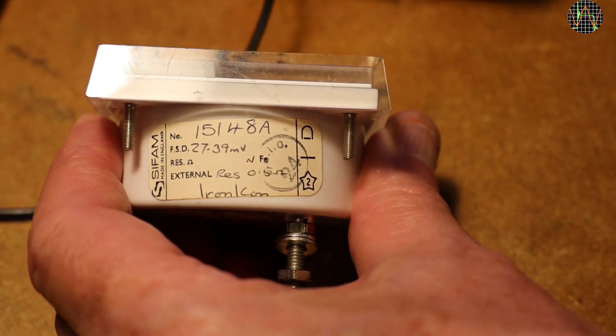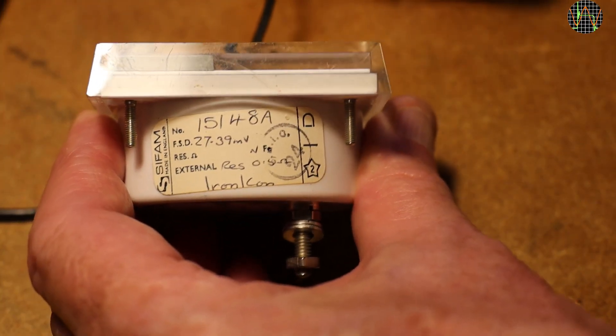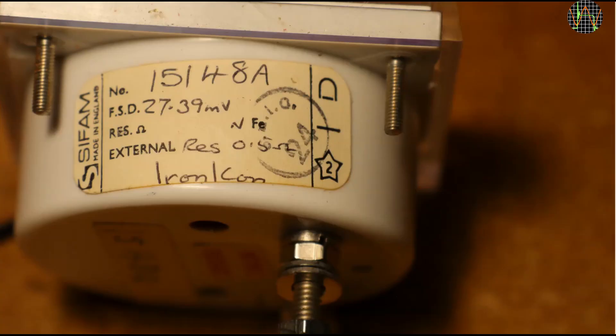There is a sticker on the side of the instrument and I pause for a moment so you can read it. FSD means Full Scale Deflection. So when 27.39 mV is applied, the needle should show full scale. I bet that 27.39 mV is the voltage produced by J-type probe at 500 degrees Celsius.